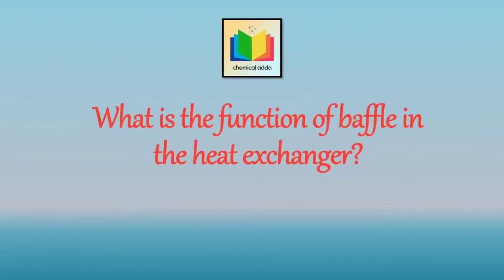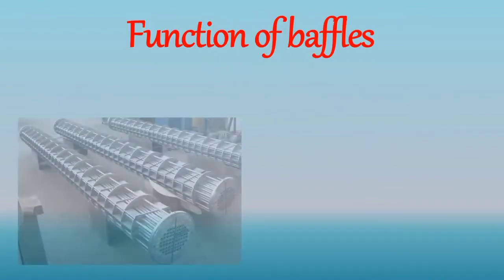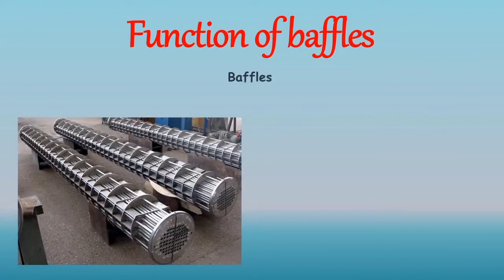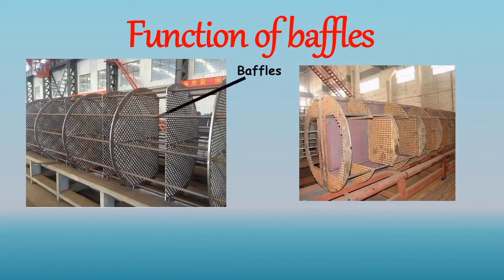So as we know, the function of a baffle in the heat exchanger: baffle is used to support tubes in the heat exchanger, which reduces mechanical vibration and leakages and failures near the tube sheet. It also enhances heat transfer by directing the flow through the shell in the desired pattern, which increases turbulence and reduces the stagnant area in the heat exchanger.